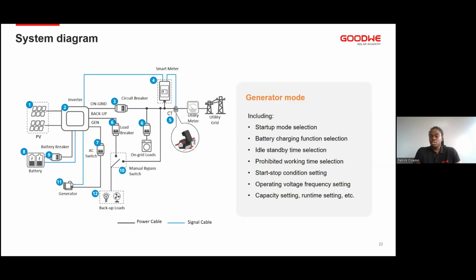All the features of the ES Unique are comfortably summed up in this system diagram. A hybrid inverter capable of connecting PV strings, batteries, grid line AC cables, local backup AC cables with diesel generator port connection. All these with the additional zero export limitation. The export value actually is configurable to meet the local allowable net metering value. So if you have countries that are trying to take in the net metering grid profile, then this is configurable for you.